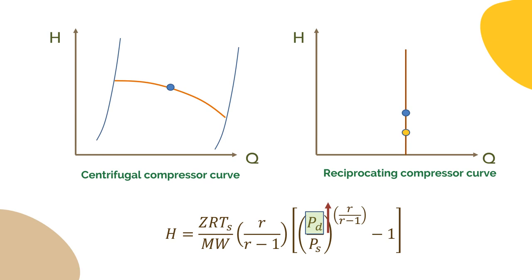As the compressor curve depends on many factors, it's always important to provide the compressor manufacturer with the applicable scenarios to check them. For this reason and as the API 617 recommends, the supplier provides the curves for both head vs flow rate and discharge pressure vs flow rate.